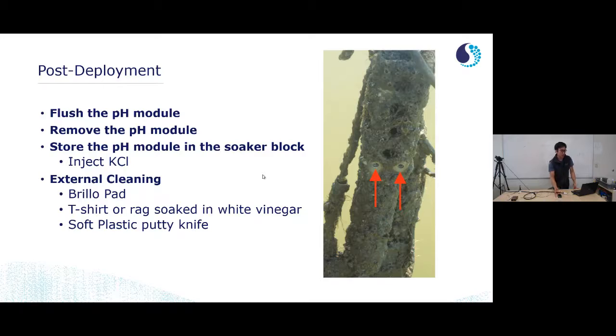This picture on the right is really awesome. It shows how effective the anti-fouling cartridges are. The intake and exhaust of the instrument are totally free of biological growth, and the inside of the instrument is totally free of biological growth too. But obviously on the outside there's a lot of biological growth going on in the water. So in this case, the anti-fouling cartridges worked really well.